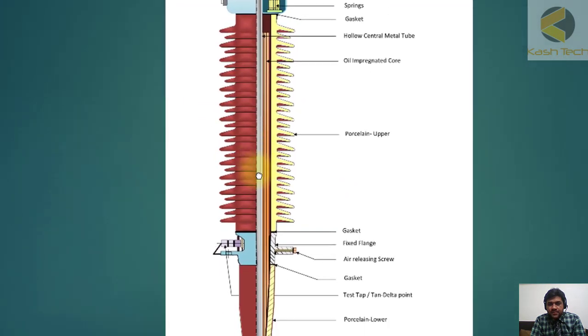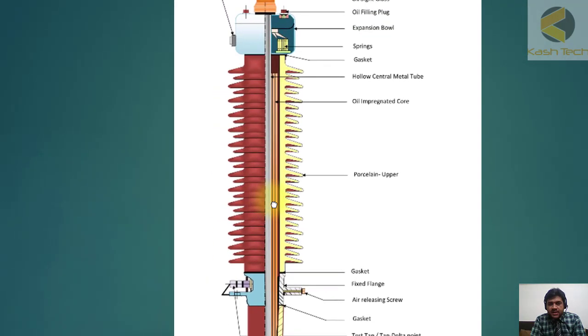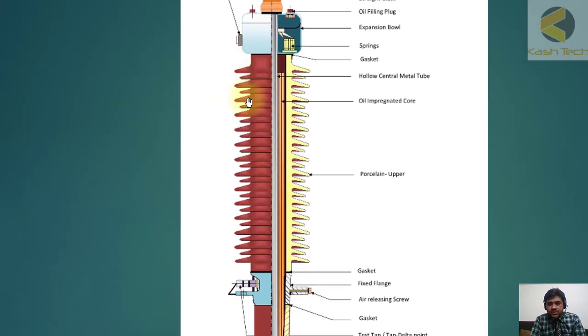Another thing you might have noticed - the bushing is not straight, it is in this zigzag format: up down, up down, up down. What is the purpose of this? If you take the straight line, the distance is less, but if you follow this path as per this bushing, the distance is much more. This method is used to increase the creepage distance.